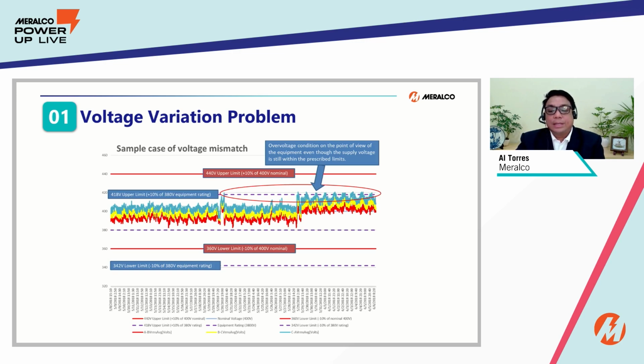However, if we are using 380 volts rated equipment, you will notice that there are instances of overvoltage from the point of view of the end-use equipment. So even though earlier we agreed that the voltage supply is still within the acceptable limits, it will cause an overvoltage problem on the equipment because of the voltage mismatch issue. So these voltage mismatch problems are very common nowadays.